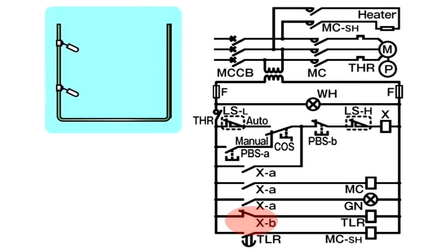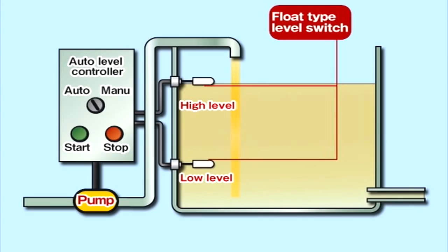As X-B is turned off, the timer's coil is demagnetised. As the fuel oil transfer pump usually operates in auto-control operation mode, the changeover switch is usually switched over to auto mode after confirming that pump operation has been initiated. Pump operation continues because X remains in self-holding state after switchover.